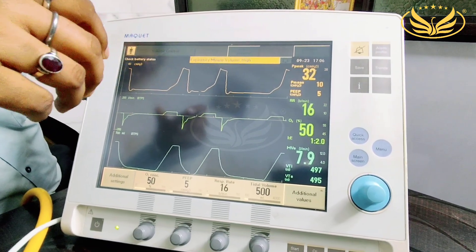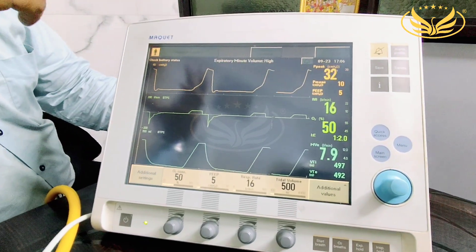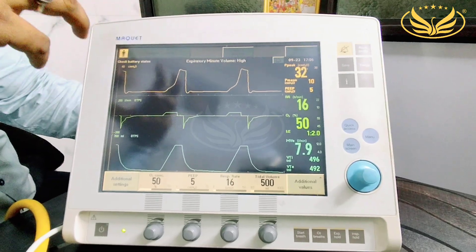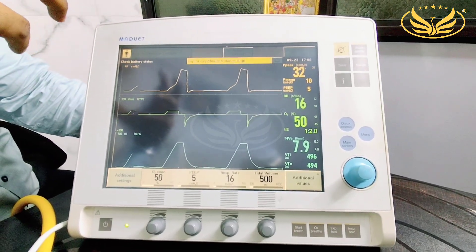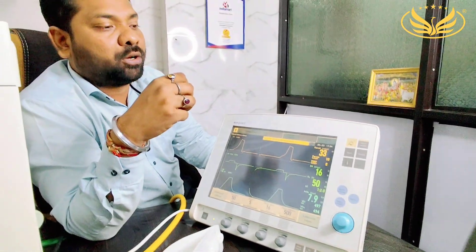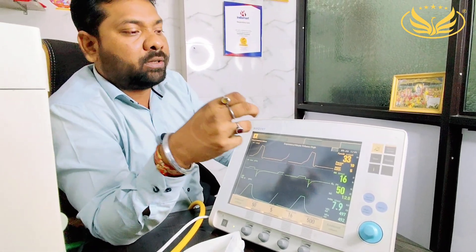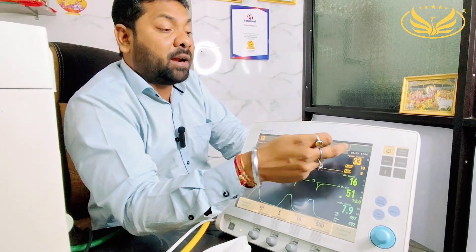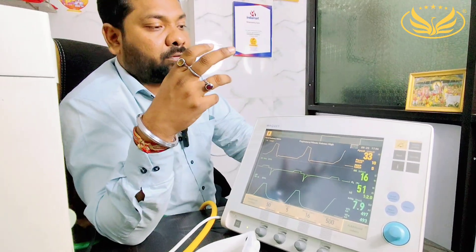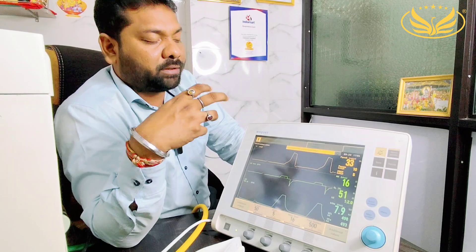In some hospitals, what we have observed is that the air pressure and oxygen pressure which has been set by the pipeline person doing the setup of the oxygen airline — suppose if we want to check how much pressure, air or oxygen, we have in our hospital — from here if we check the status, you can see all the details.